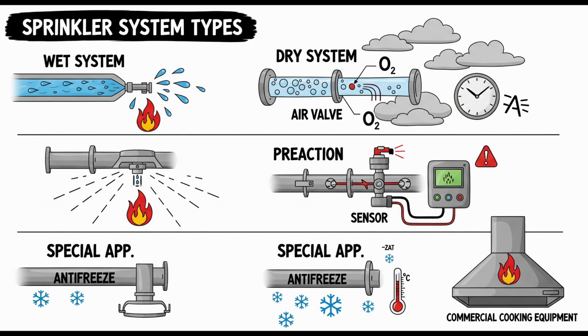Absolutely. The air supply connection must be at least half an inch in diameter and enter the system piping above the priming water level of the dry pipe valve. Above the water line in the valve. Yes. A check valve is required in this connection, with a listed or approved shutoff valve, like a ball or renewable disc valve, on the supply side of the check valve.